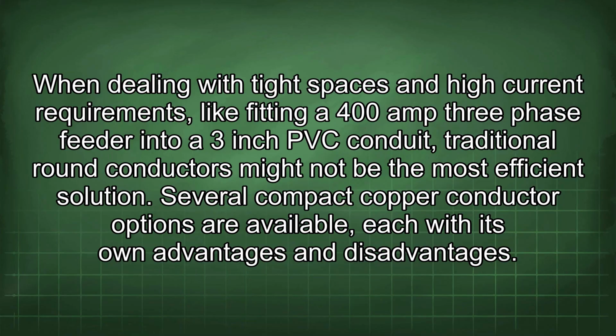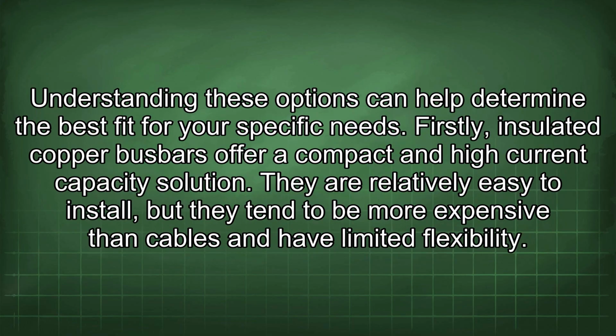When dealing with tight spaces and high current requirements, like fitting a 400 amp 3-phase feeder into a 3-inch PVC conduit, traditional round conductors might not be the most efficient solution. Several compact copper conductor options are available, each with its own advantages and disadvantages. Understanding these options can help determine the best fit for your specific needs.